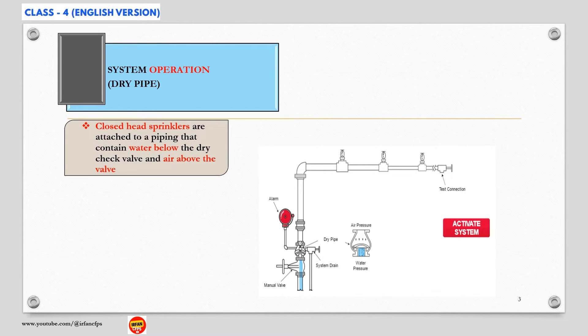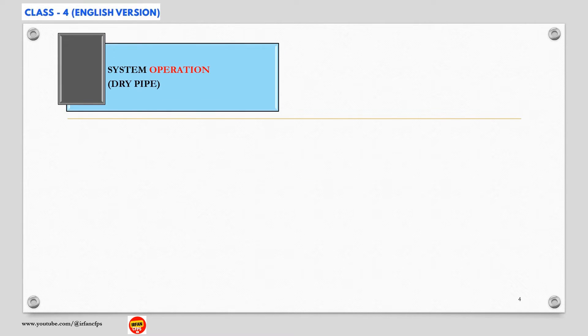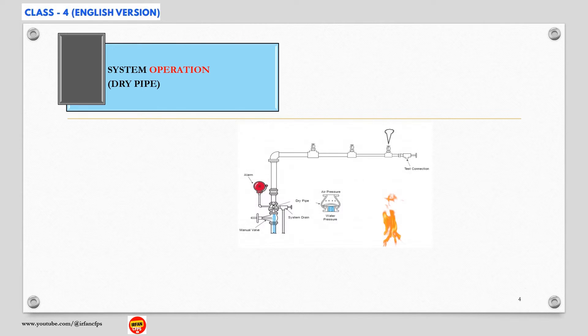As we discussed in our previous slide, in this system, closed head sprinklers are attached to a piping network that contains water below the dry pipe valve and pressurized air above the valve. Like a wet pipe system, when the temperature at the ceiling becomes hot enough, the glass bulb or fusible link of the sprinkler breaks.